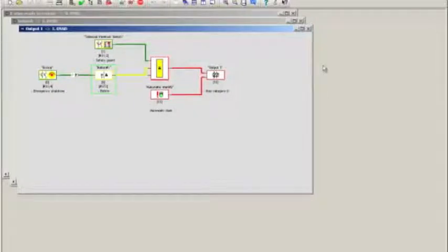Okay, now we're in diagnostics mode, and what we can see is that the solenoid interlocking switch is giving us a green, a true signal. That's because the key is inserted and the switch is latched. Also, the e-stop is released, but the button function only provides us with the yellow ready signal. That's simply because I have not activated the S72 input. So as soon as I do that, everything starts up. So let's just check this out real quick.